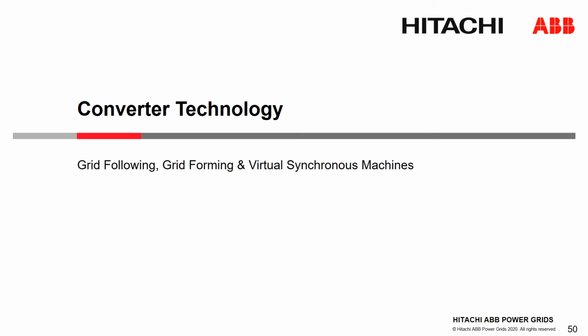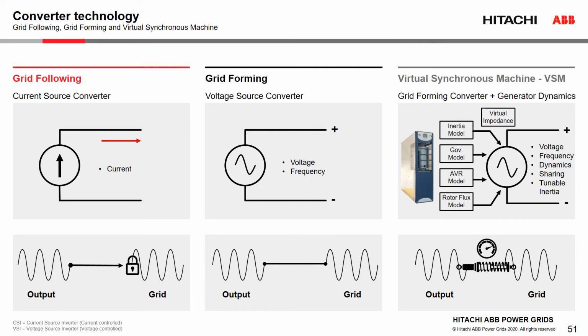So we'll now discuss converter technology. Here we have three types of converters. On the left, we have grid-following converters or current source converters. Nearly every PV and energy storage system connected to the NEM today is a grid-following converter. Grid-following converters have a mechanism called a phase lock loop, which we can see at the bottom left. These devices lock onto the grid waveform and follow the grid, hence the name grid following. These devices try and push current onto the network to provide energy as a service. The challenge with these converters is that if the grid waveform is compromised, there can be challenges with instability, because they have challenges following the grid during post-fault conditions or other such contingency events.